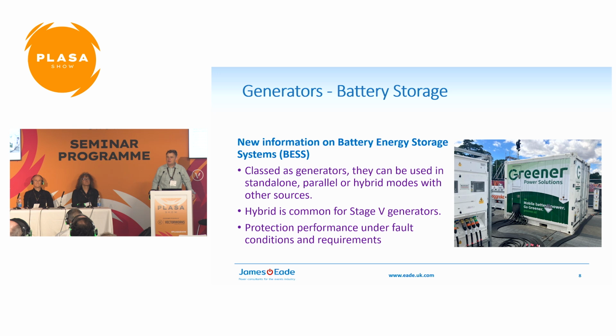Common now with stage 5 generators, where you have issues with needing to keep the engine working hard so that it remains hot, because otherwise the exhausts clog up with the urea from the AdBlue. So again, running generators on low load, and particularly in parallel, is not really a model we can sustain anymore with the modern engines. So battery storage is becoming quite common in hybrid mode to actually power the loads, and then the generators are used to charge the batteries.